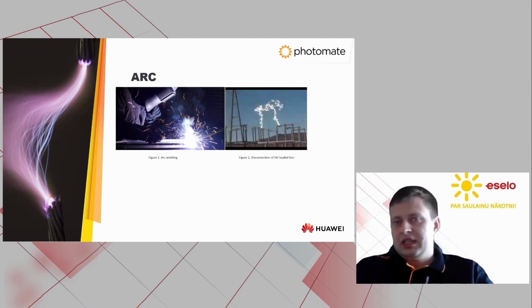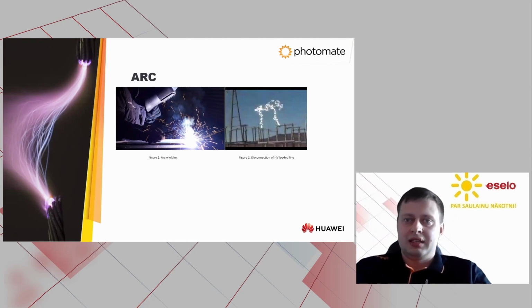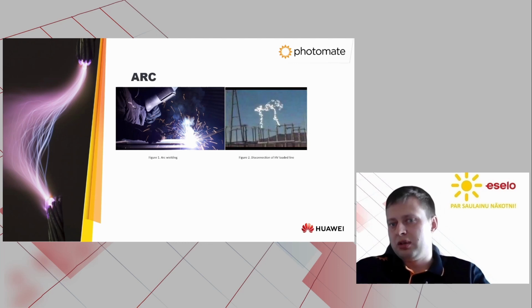So to start the safety feature topic, it is important to understand that the primary hazard associated with photovoltaic systems is the risk of fire. And one of the main reasons for this risk is a phenomenon called arc flash. Arc flash occurs when the voltage between 2 points in the system exceeds certain limits, which can cause atmospheric air, which is typically an insulator, to become a conductor for a brief period of time. This breakdown of the insulation creates an arc, which can lead to fire.